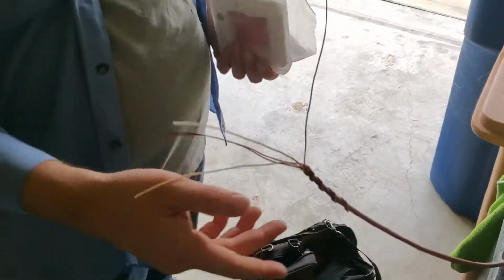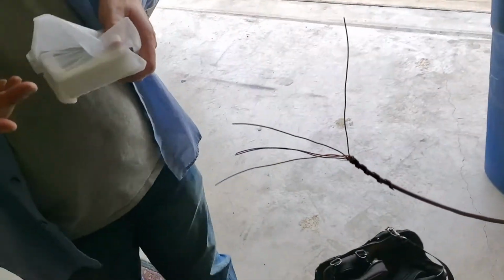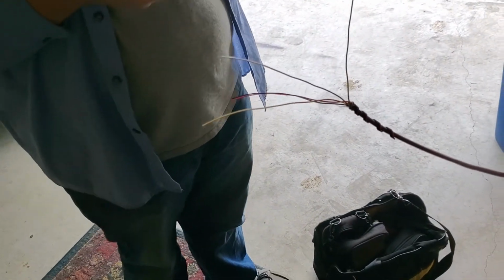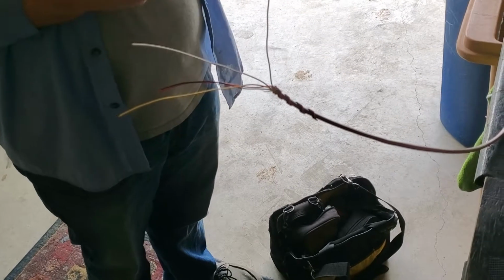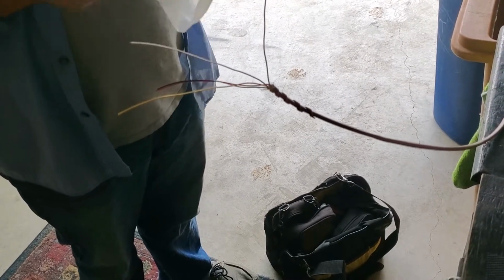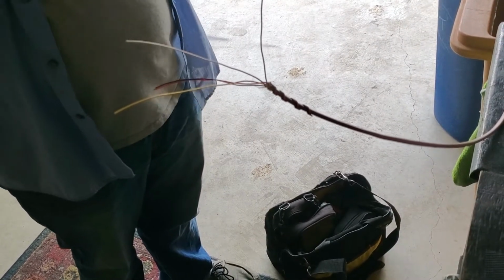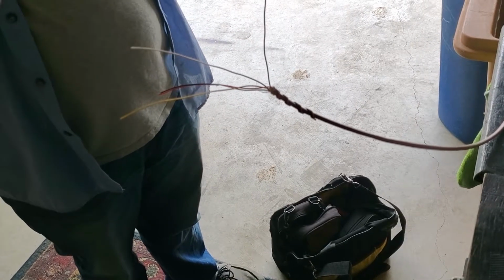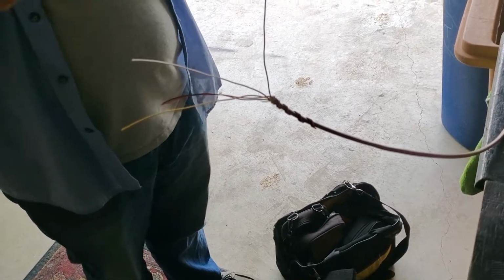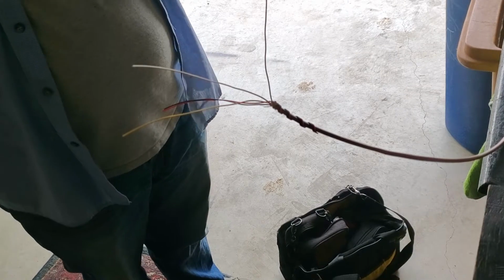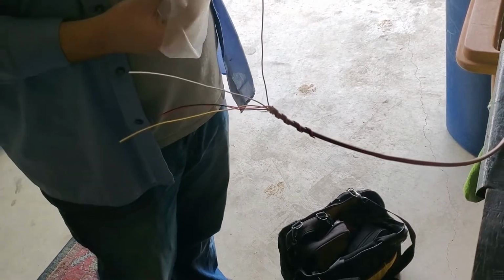If you come across something with 2 wires, you know you need a minimum of 5. But what I'd do is run the equipment first before you change the thermostat out. Go to the existing thermostat, put it in cooling mode, make sure the cooling comes on. Put it in heat, make sure the heat comes on. That way you know whatever they had before was working.